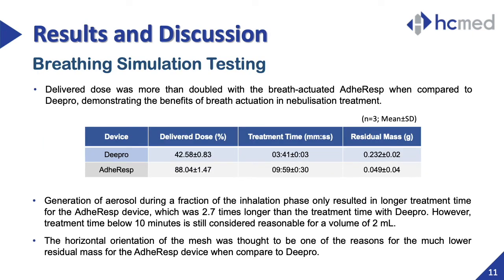Mean values for delivered dose, treatment time, and residual mass are displayed with standard deviation in this table. The delivered dose was more than double with ADHERESP at 88%, when compared to Deepro which remained close to 40%, demonstrating the benefits of the breath-actuation function. In ADHERESP, medication was aerosolized during inhalation only. The treatment time was 2.7 times higher for ADHERESP; however, treatment time below 10 minutes is still considered reasonable for a volume of 2 mL. The horizontal mesh module of ADHERESP played a key role in the low residual mass post-nebulization, as the medication concentrated above the mesh membrane during the entire treatment.